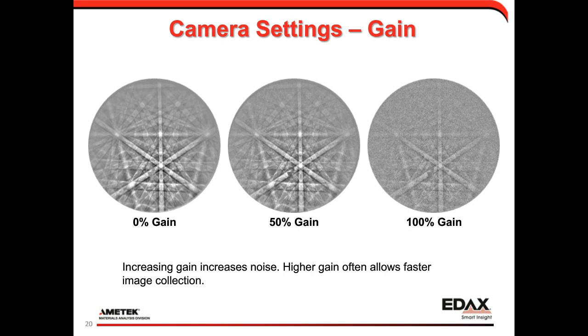The question I also just got in is, why is the upper half less focused? This is usually not a positioning issue, but it's because of where the pattern center is itself. The pattern center is usually towards the upper part of the image, but it changes with the geometry of what scope we're dealing with. In this case, we're probably dealing with a system that had the pattern center more towards the middle or maybe even towards the bottom. This is just a scope geometry issue.